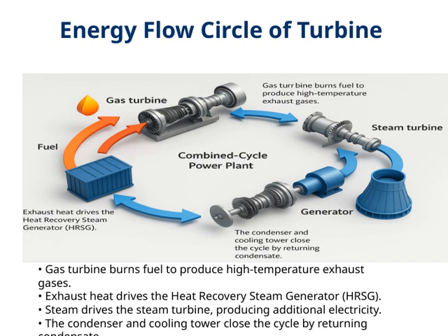Next, this exhaust heat is used to drive the heat recovery steam generator, or HRSG. This is a key component because it captures the waste heat and converts it into steam. That steam then drives the steam turbine, which produces additional electricity, making the process more efficient.